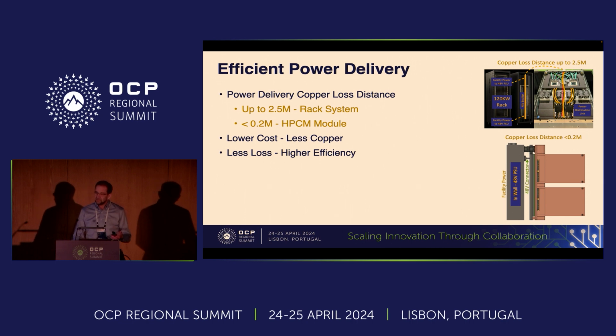Focusing on efficient power delivery now, just to remind you back to the NVIDIA Blackwell, we said that we had up to 2.5 meters of distance between facility power and the point of loads of the Blackwell chips. With our design, you can see in the bottom right, the facility power is in that wall of compute through a 48-volt power step down, and only literally a couple of inches, or less than 0.2 meters, between the facility power and the point of load for any one module. So we've got lower cost potential with less usage of copper, and potentially a lot higher efficiency as well, because there's less drop across the connection.